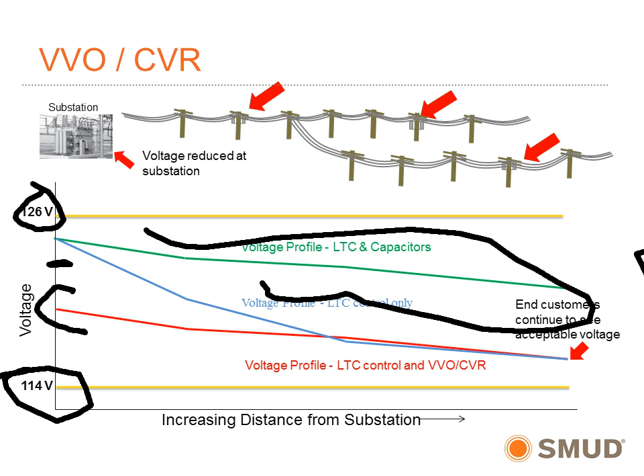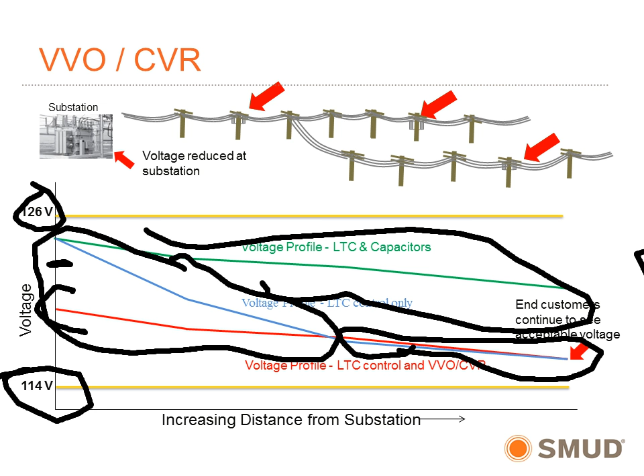Coming back to the VVO, we boosted up the voltage on the line, and then we can go to the substation and adjust the tap changer. Looking at this red line, you can see we can reduce the voltage across the line. What you end up with is, specifically in this area, energy savings. So if you do it according to the way this chart is, the people at the end of the line probably aren't going to see as much CVR benefit as those at the start of the line.